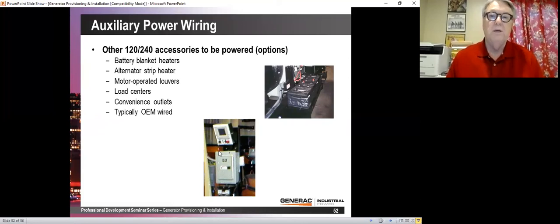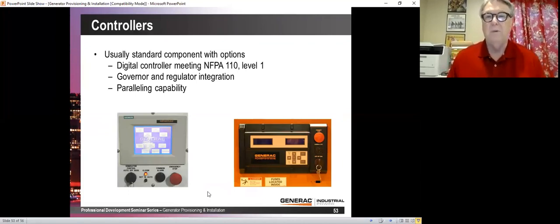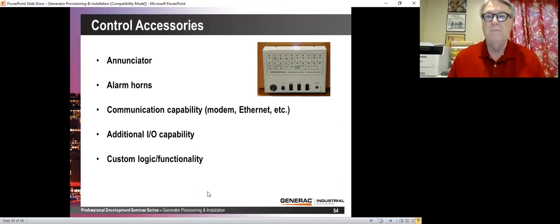That's an option. Cost what, $300 or something to put in there, but it can be nice because then you can bring one feed into that, and then your controller and your block heater and all are on separate breakers coming out of that. It's a nice feature, not standard on any generator, but available as an option. Here are your controllers. We talked about those last week. Make sure that if you have a legally required emergency generator that meets NFPA 110 level 1, that you have a remote annunciator, and there is a copy of that.